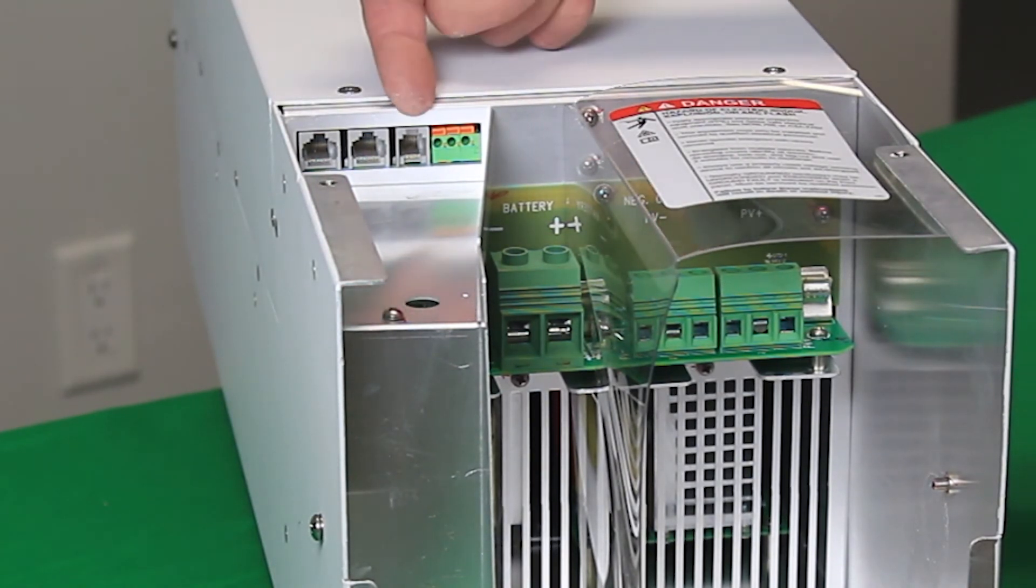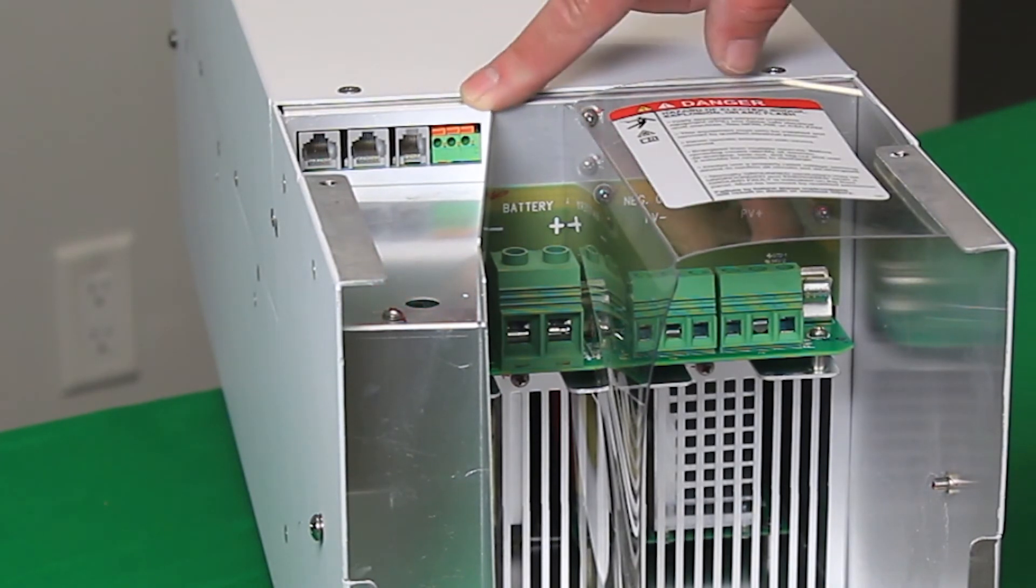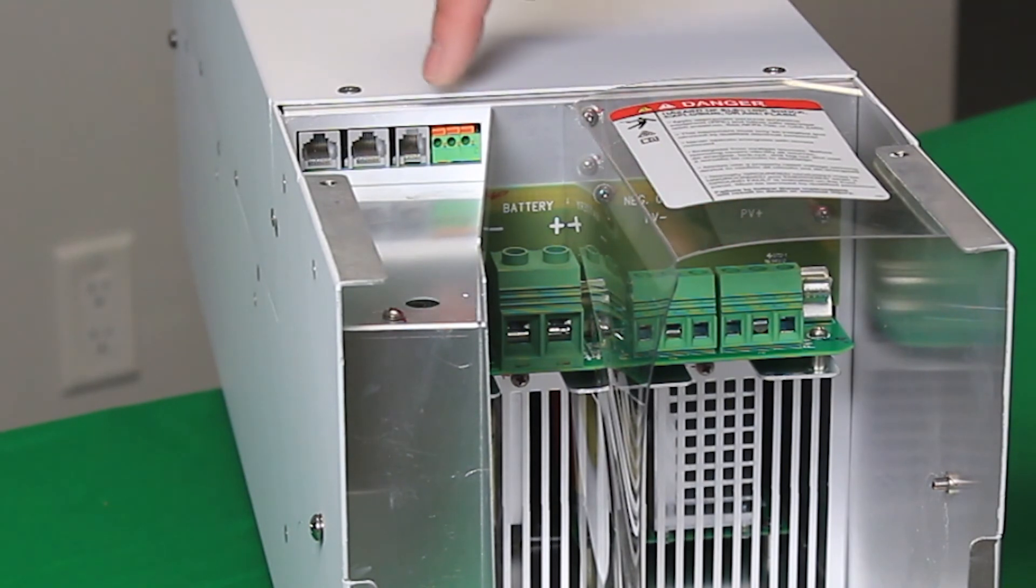Here we have the RJ12 connector for your battery temperature sensor. And then here is the auxiliary port. The auxiliary port is a dry relay contact with a common, a normally open, and a normally closed position. It can pass through up to 60 volts DC, up to 30 volts AC, and up to 8 amps.